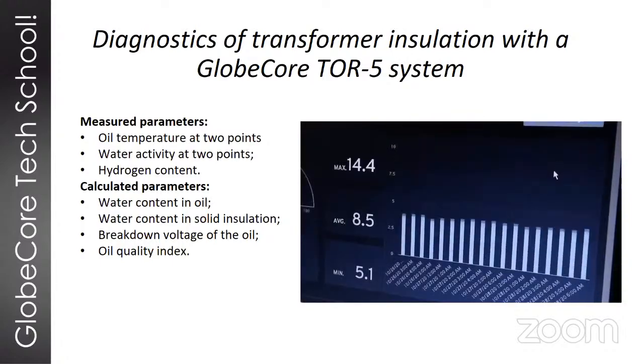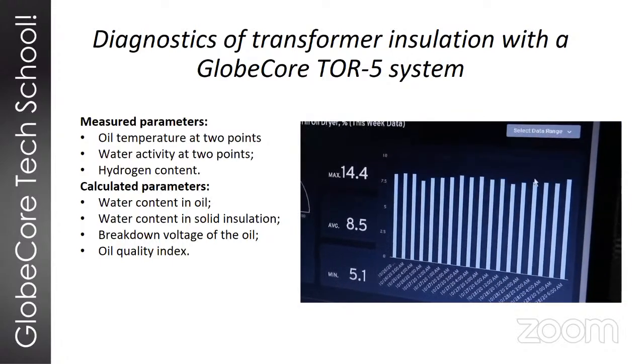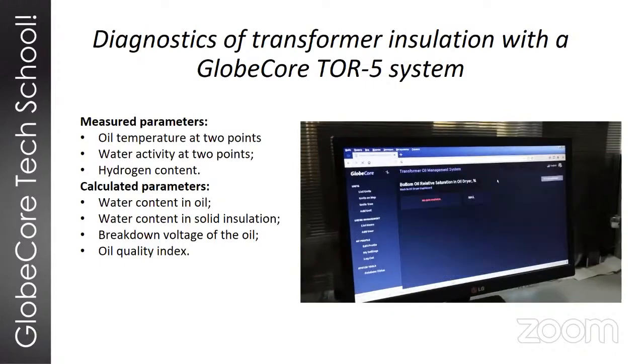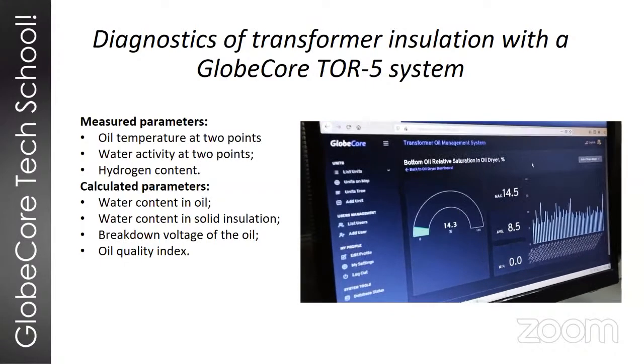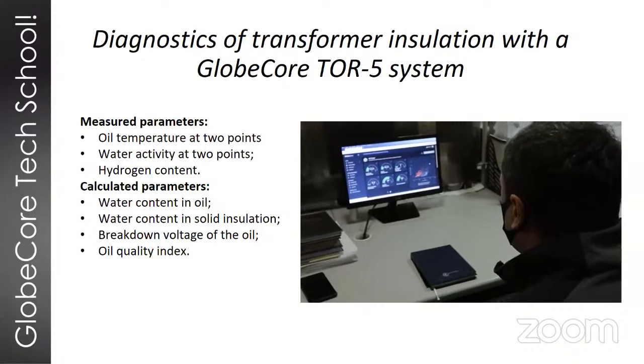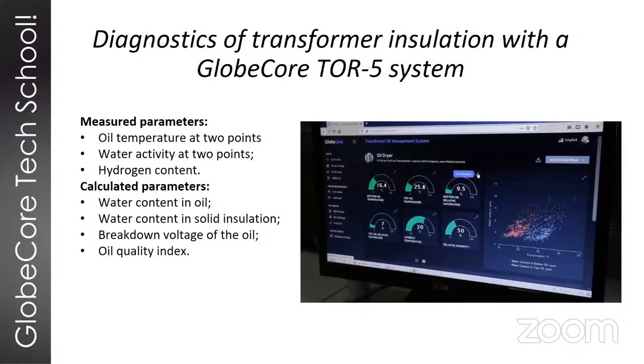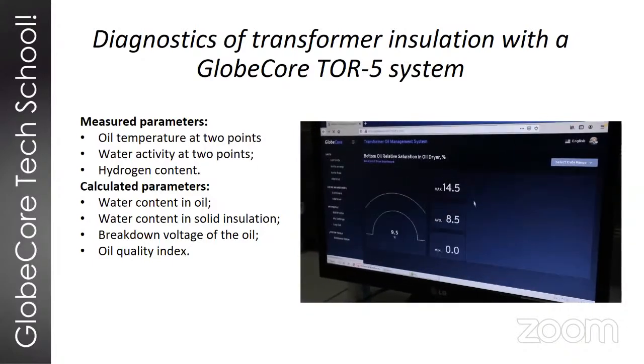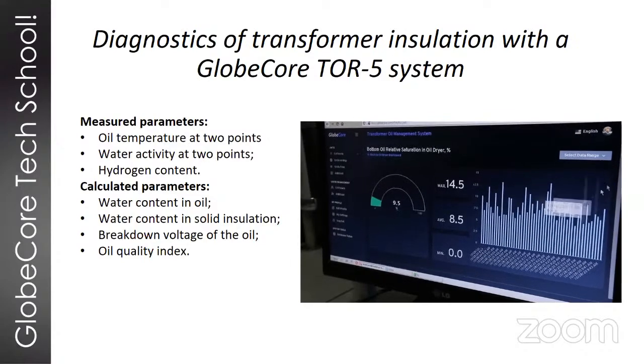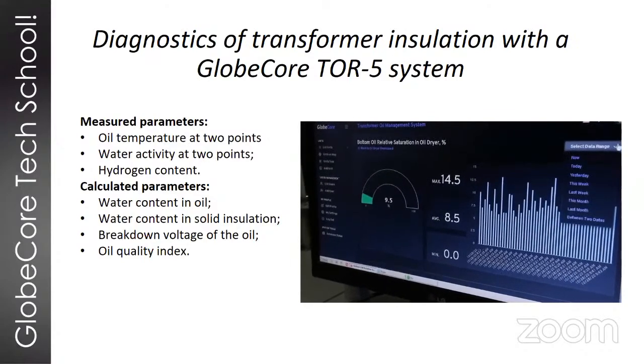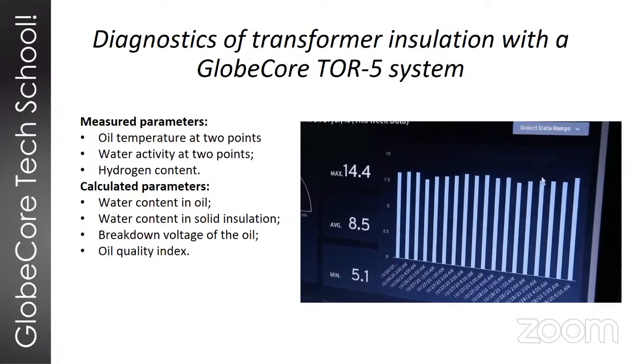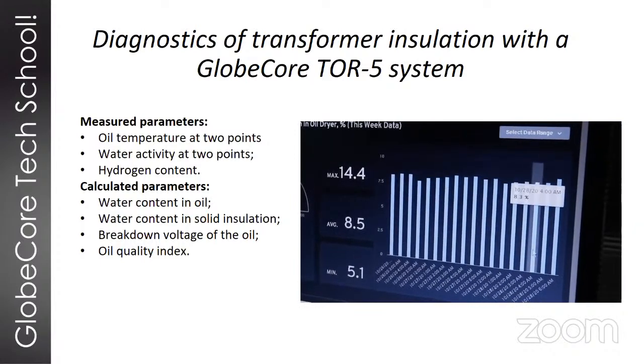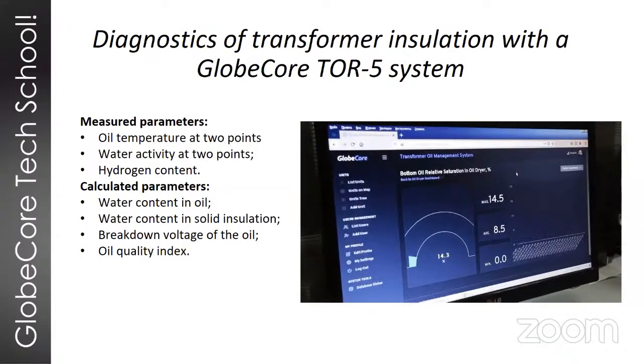100% dielectric strength corresponds to a relative humidity of less than 20%. If the relative humidity goes up to 60%, then the dielectric strength drops down to about 30%. Another parameter that we calculate here is the oil quality index, and this may be something new for you, and more on that in just a minute.